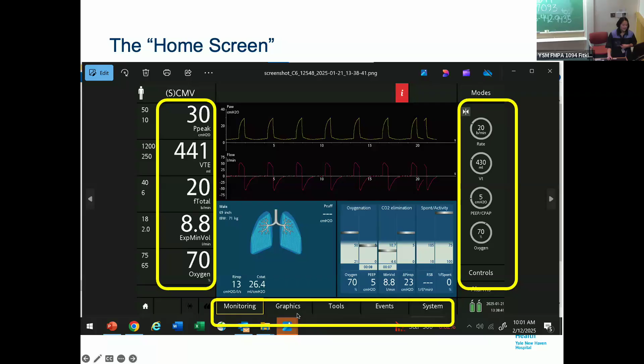The next thing I want to draw your attention to is on the right side, right under the label modes. This is the settings of the ventilator. What you'll see here that's missing is the setting for flow. On the Aveas, that's readily available on the first interface, and we didn't have to toggle looking for it. But the flow is not available here at first blush. You do have to click in to get more information about that. And it's correlated, so on a pressure mode, the inspiratory time, you also have to click on it to get it. And then over here, these are tabs that allow you to toggle through different things and get access into the ventilator. I'll go through that in a second.